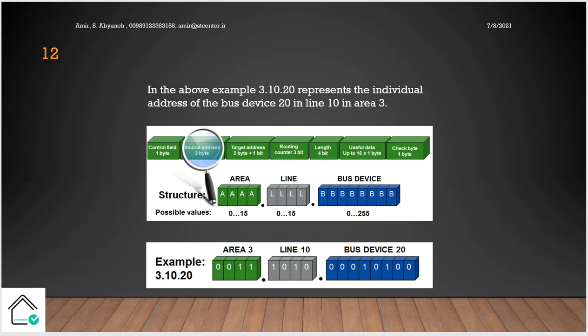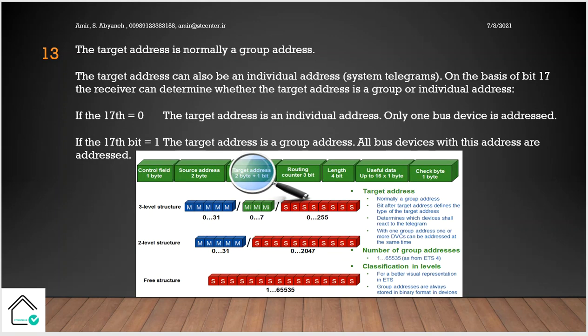The destination address is the group address during the normal operation of the system. For example, the sensor sends the telegram to the actuator, so the destination address is a group address of the relay actuator. But during the commissioning or downloading, the destination address is a physical address. When you download from your PC, the target address is the device physical address. But during the normal operation, the target address or destination address is the group address.